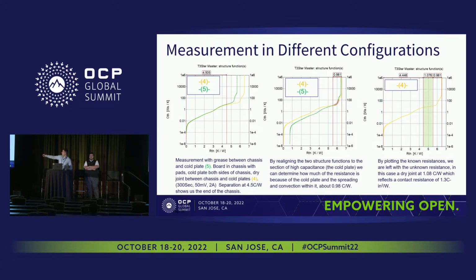What we did after was shift the green curve to the right and overlap the end of the two curves. You see a sudden increase in the capacitance at this area — that's where the heat gets into the cold plate. If I mark these two lines on my original function, that carves out approximately 1.07 to 1.08 Kelvin per watt, and this is the region which stands for that contact thermal resistance.